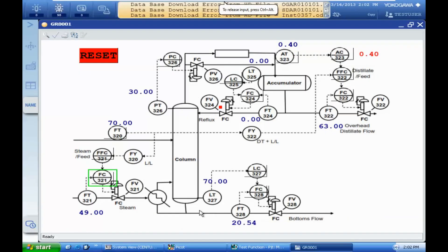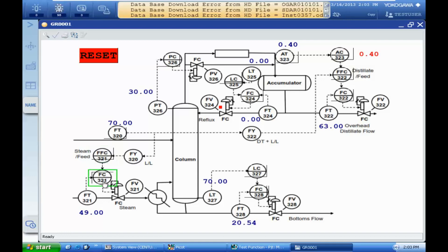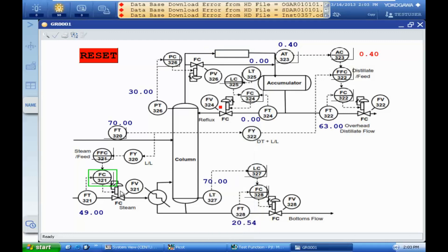This is the simulation environment in CentumVP. We will change the Inlet Flow. The value of Inlet Flow will determine the amount of steam here. The ratio is constant at 0.7, and the output of the ratio control is determining the set point for the steam inlet or steam flow to the exchanger.